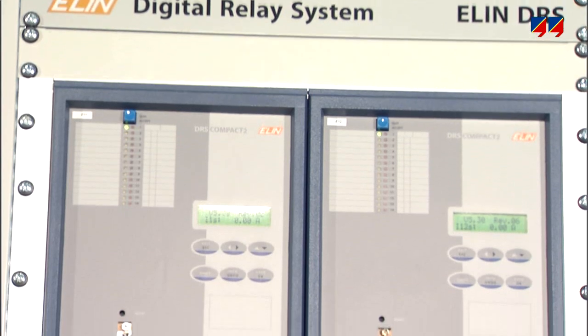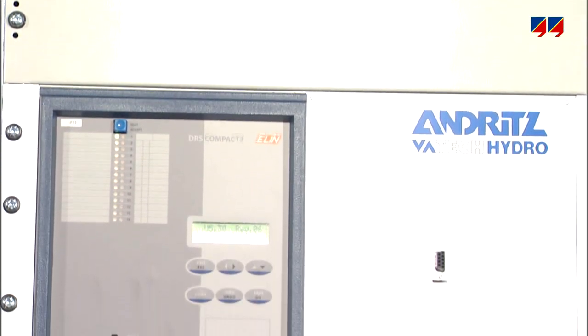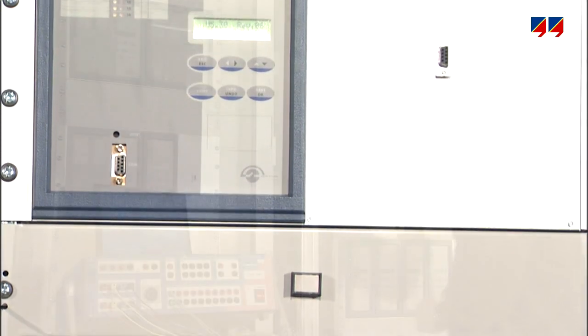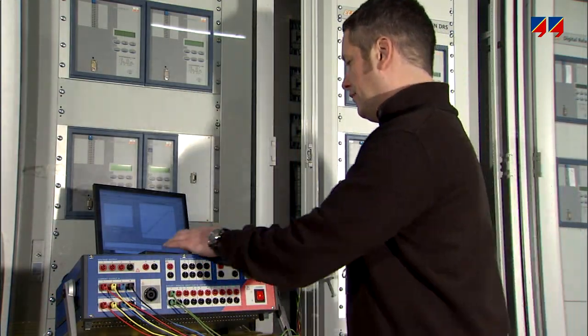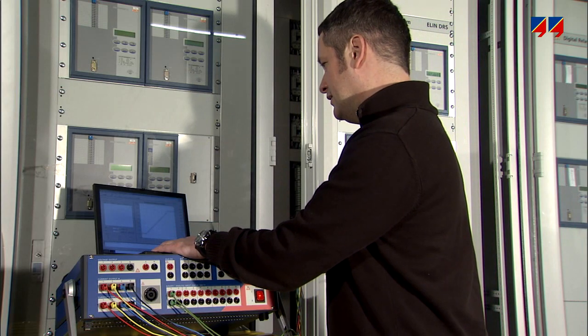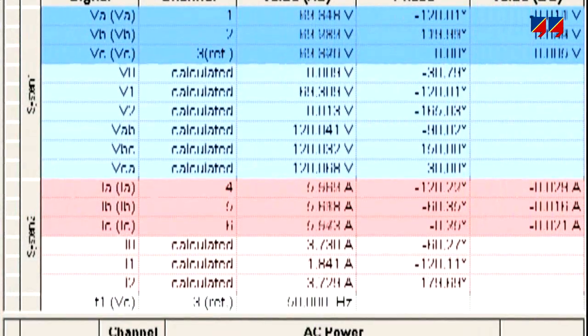Many customers use the CMC 256 Plus for testing protective relays of all types. For such protection testing, the CMC can measure the response time of wet or dry contacts with 10 binary inputs. Using these inputs together with the Analyzer option turns the CMC 256 Plus into a 10-channel analog measuring and recording device.